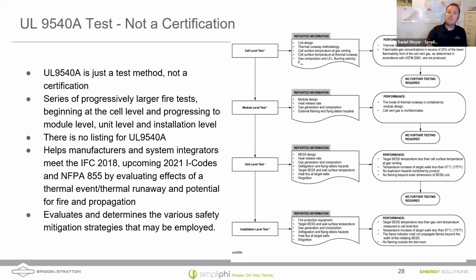I can pull out where that is and look for that. Most of the time when we're asked about spacing requirements, what's referred to is what has passed the UL 9540 system level certification, and the UL 9540A test informs that certification. So if we did the 9540 with 6 inches of spacing, we can use that for our install. I'm not aware of specific spacing requirements in NFPA 855 other than the 36 inches in front of the equipment.